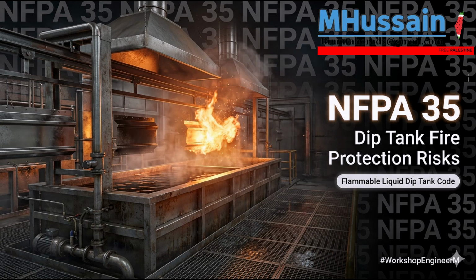Got it. So for a smaller vessel, say holding up to 275 gallons, you need a minimum of 5 feet from the property line. That's not too bad. Right, but for a massive 50,000-gallon tank, the baseline setback is 30 feet from the property line and 10 feet from the nearest public way. Okay, but that 30-foot setback is just the best-case scenario, isn't it? It is. Because the standard introduces multipliers based on the internal pressure of the vessel and the chemical stability of the liquid.